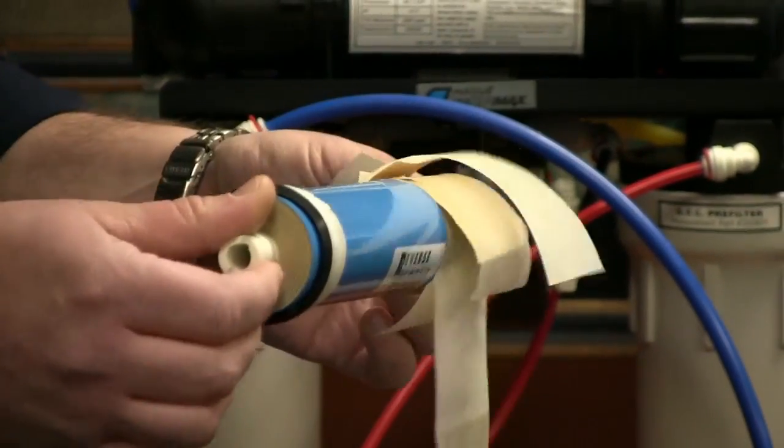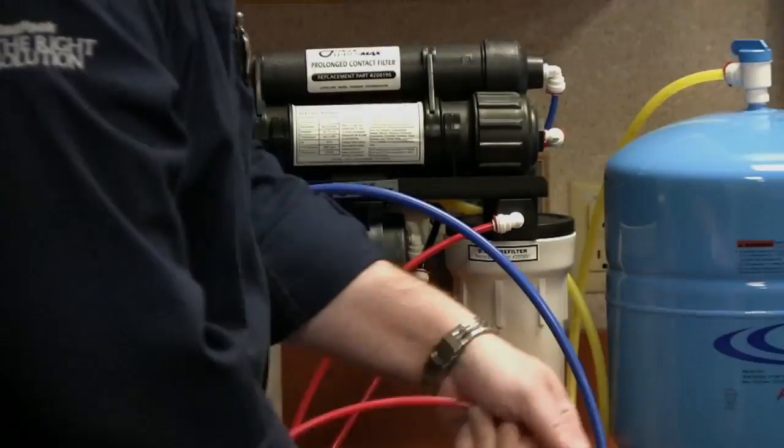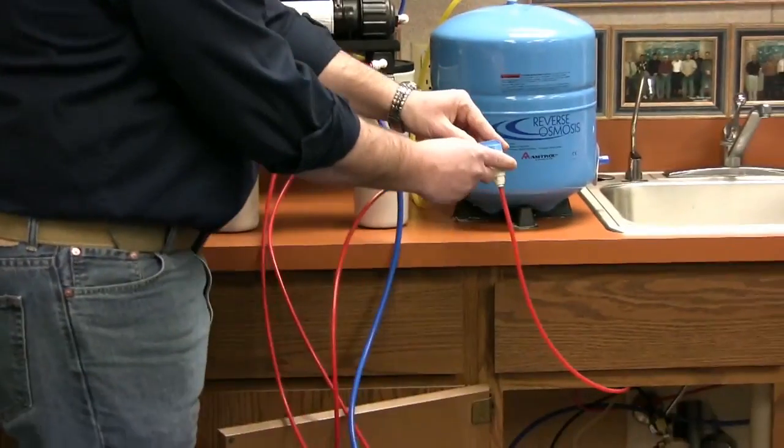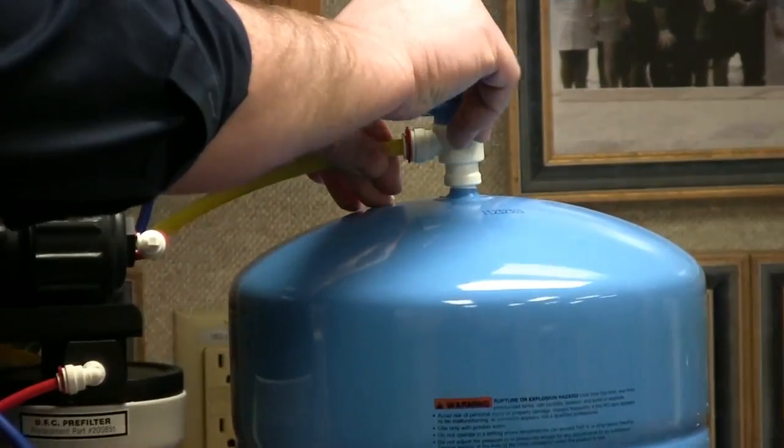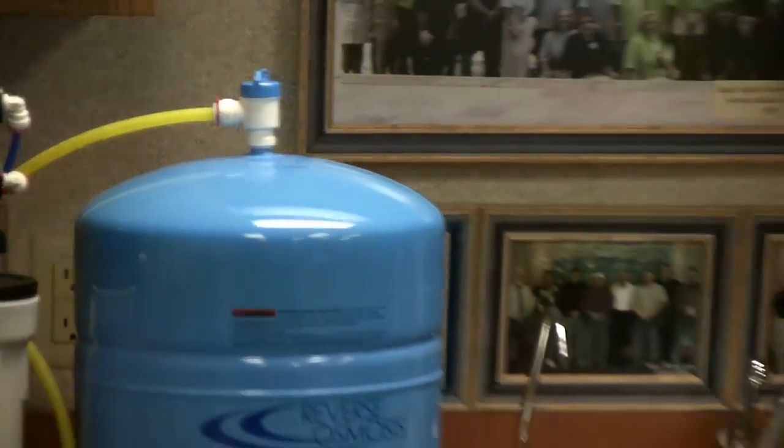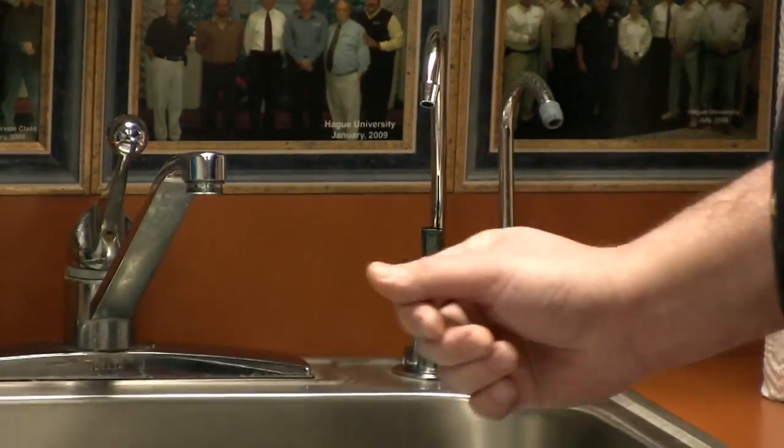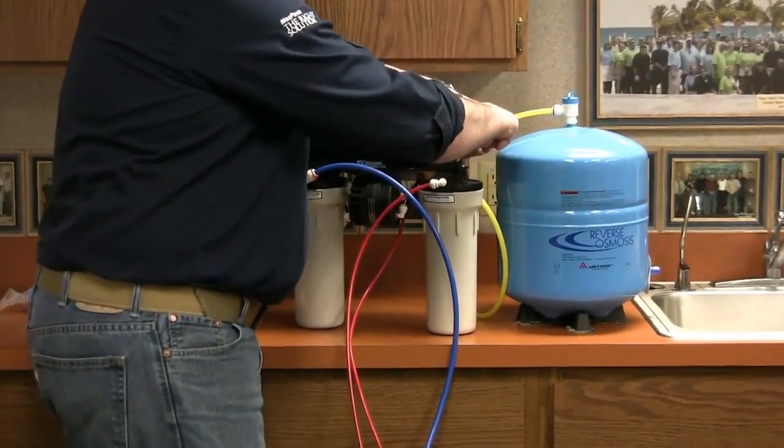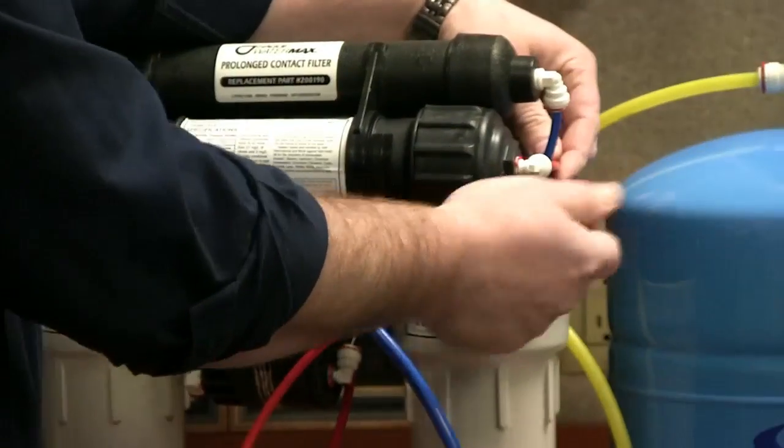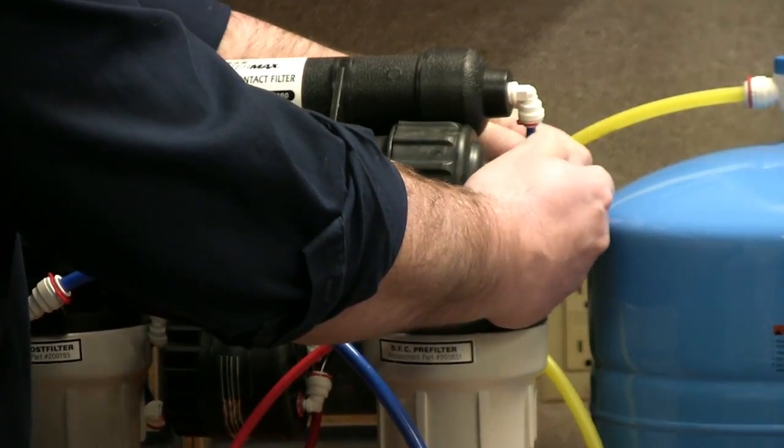Definitely don't let them freeze or get tossed around in the truck. So to replace the membrane you'll want to shut off your feed water supply, shut off your storage tank, and then depressurize the system. Once the system is depressurized, disconnect your feed line into the RO module.